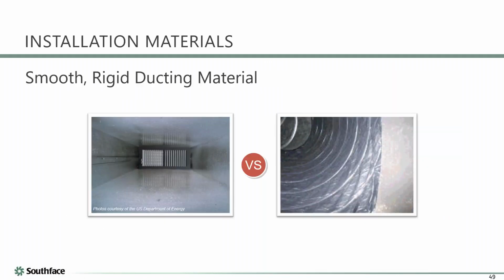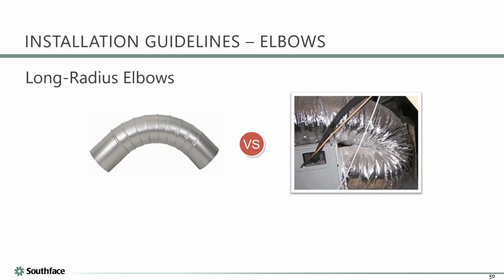That was another $1 million house I took that picture in. This is a great example showing that if flex duct is really pulled tight, you're going to get about 15 to 20% less airflow than the same diameter round metal duct. I know that's square. If flex duct is just laying there or run poorly in any way, you're going to get way less airflow than that. You might get 30% less airflow, or 40% less, or half the airflow.